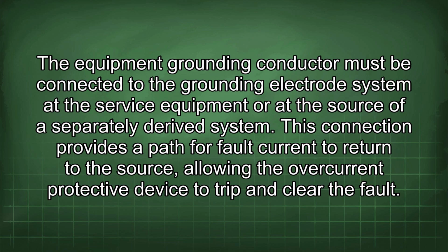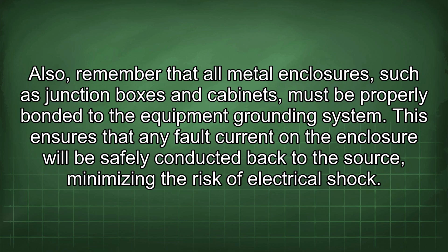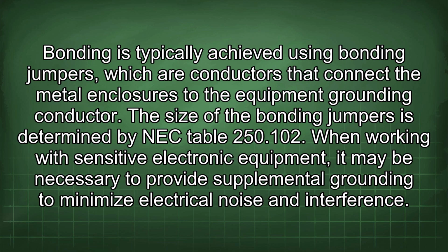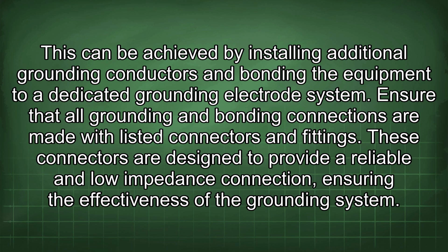Also, remember that all metal enclosures, such as junction boxes and cabinets, must be properly bonded to the equipment grounding system. This ensures that any fault current on the enclosure will be safely conducted back to the source, minimizing the risk of electrical shock. Bonding is typically achieved using bonding jumpers, which are conductors that connect the metal enclosures to the equipment grounding conductor. The size of the bonding jumpers is determined by NEC Table 250.102. When working with sensitive electronic equipment, it may be necessary to provide supplemental grounding to minimize electrical noise and interference. This can be achieved by installing additional grounding conductors and bonding the equipment to a dedicated grounding electrode system.